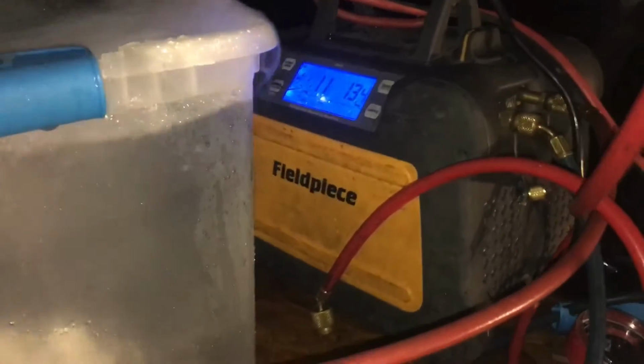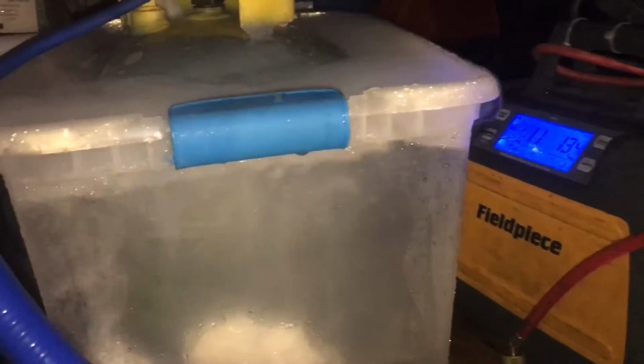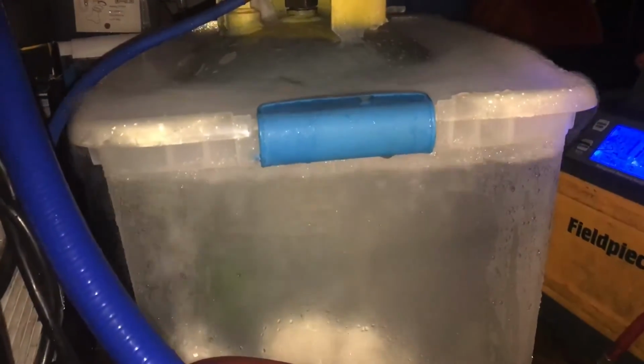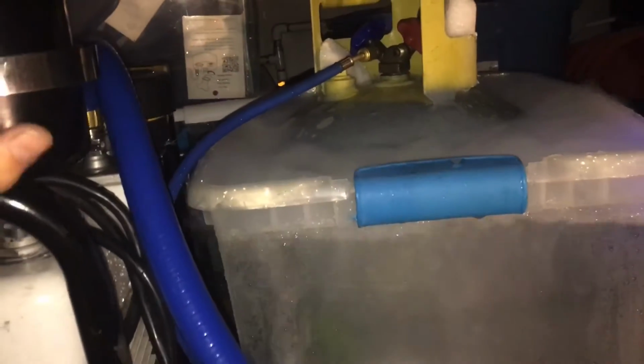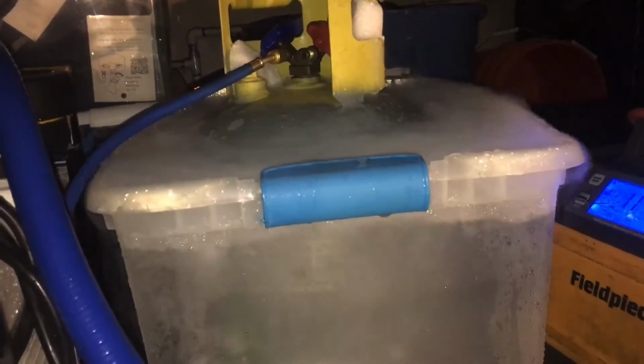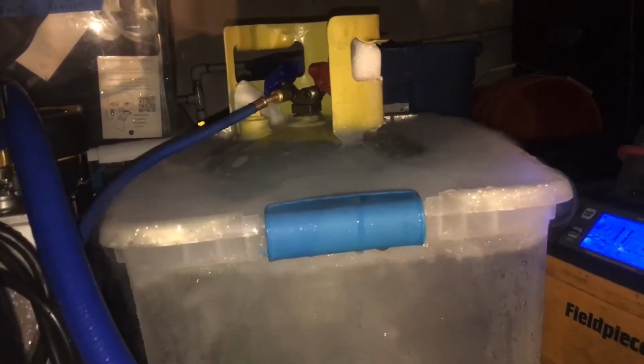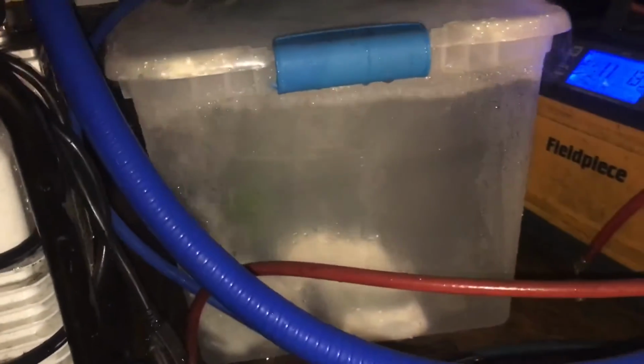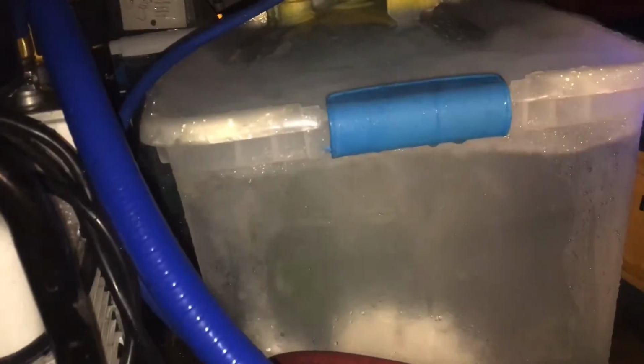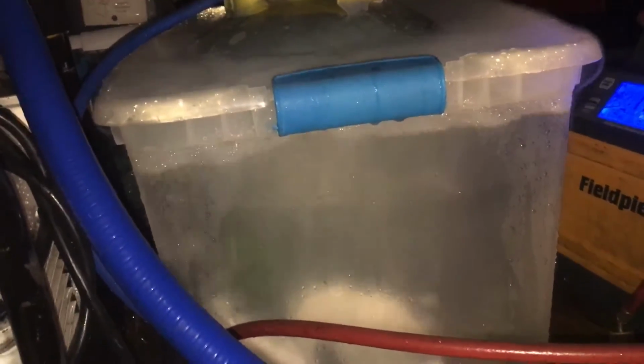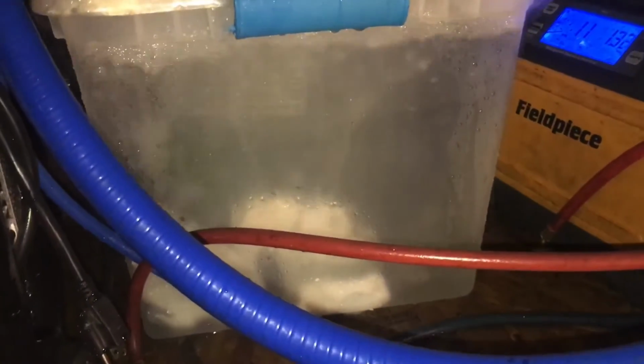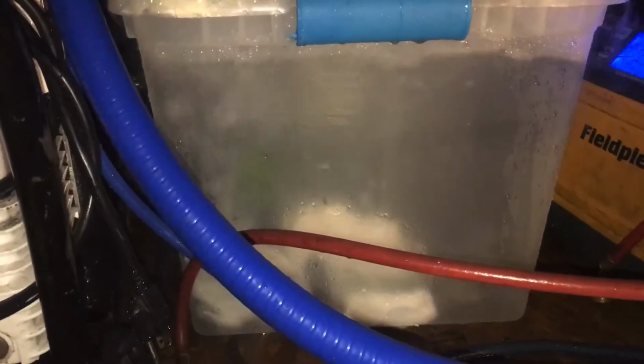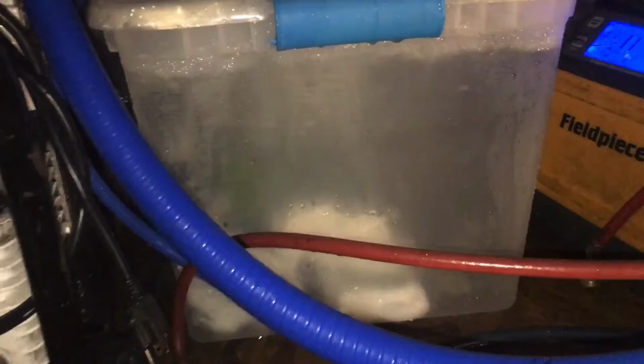and this is all caused by a technician who came out here after new management for HVAC and decided, with this system having 9 plugged filters on air handlers, completely packed plug with barely any airflow over them, one with a dead fan motor, he decided the system wasn't cooling very well, so he dumped another 20 pounds of refrigerant in the system. And so the result is, you do not do that on a VRF. So now the customer is going to be charged $1,000 plus for recovery and refill back to factory spec. And they've been down for 2 days now, partly yesterday for recovery time and a full day today doing recovery.